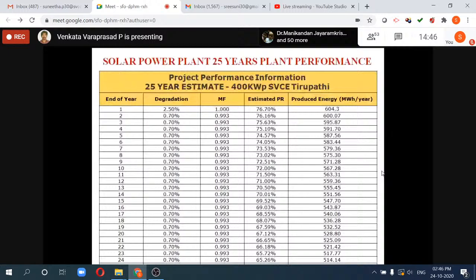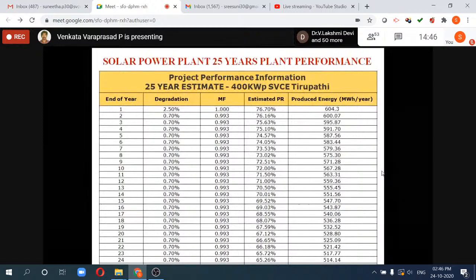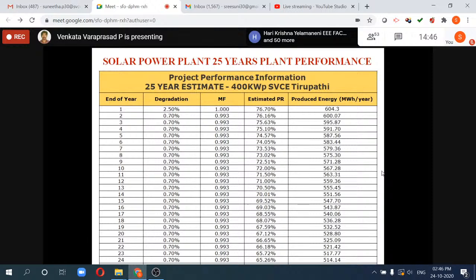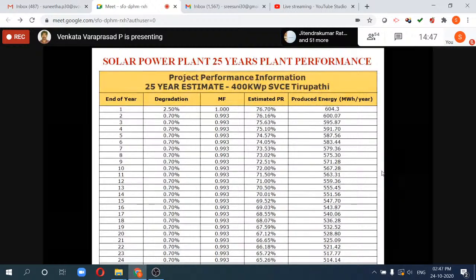So at the beginning, I mentioned solar generation. Here we need to follow some terms and conditions. In the terms and conditions, we have seen point five: the plant performance for its lifetime of 25 years should be like this report. For 25 years, estimated 400 kilowatt is the projected performance information they will give. So the first year it's 2.5%, and for subsequent years the common degradation value will be 0.7%.